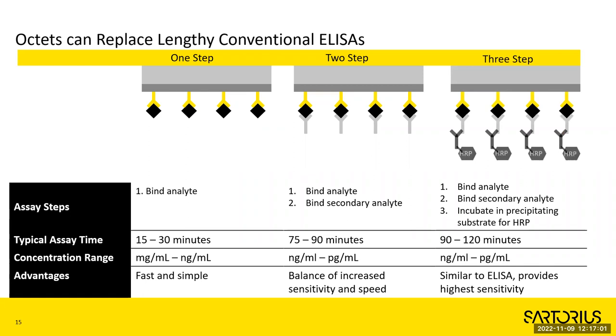You take a third molecule attached to an HRP enzyme, dip it into a well containing metal DAB. When hydrogen peroxide is added, the metal precipitates onto the tip of the sensor. That precipitation is very large and amplifies your signal at least 10-fold. Most customers who want to replace an ELISA and move to the Octet don't actually need to go that low in concentration - the color change from the HRP read on the plate reader is a typical ELISA situation. Most people can actually skip that step and switch to the Octet.